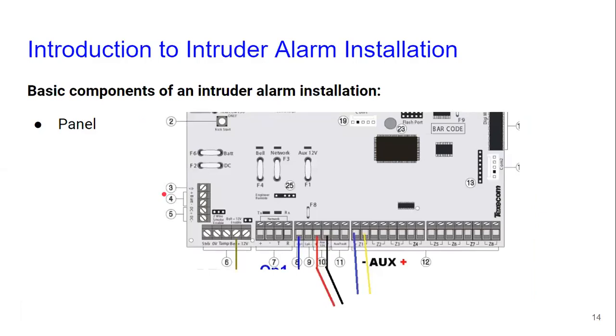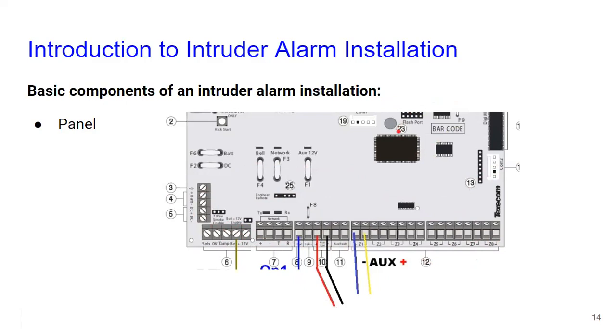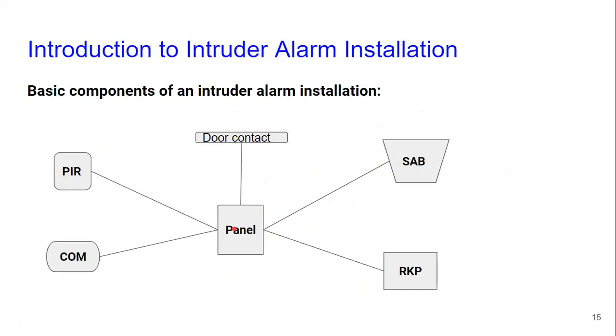The panel is like the brain that controls the whole system — everything normally has to be wired to the panel. You have zones one through eight, bell connections, keypad connections, speakers, auxiliary output, fault indicators, and battery DC terminals. There are also ports you can connect to a laptop. It's a star-type connection where everything connects back to the panel. This makes installation easier — you can hire first-fix engineers to pull cables from each sensor back to one central point where you site the panel.